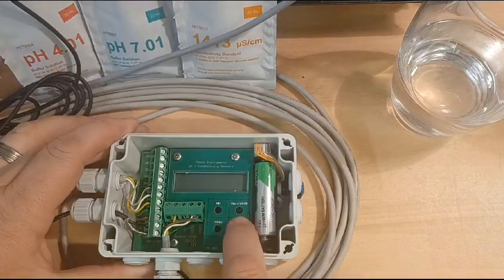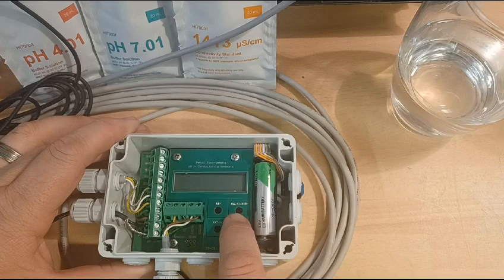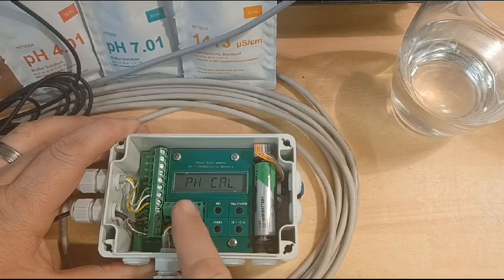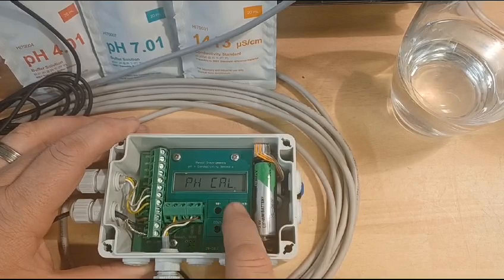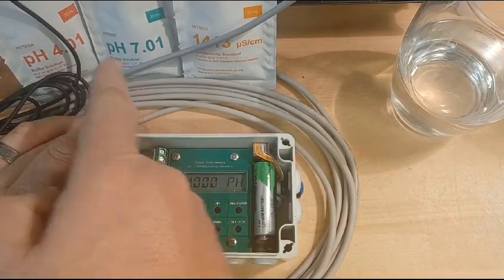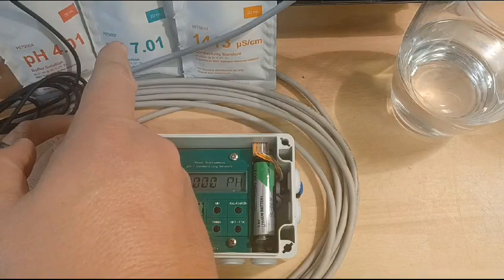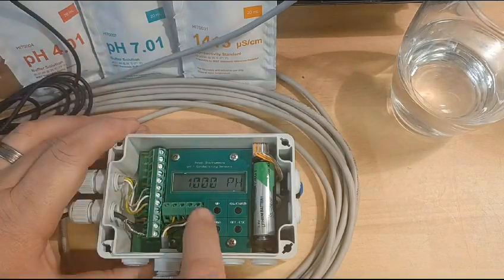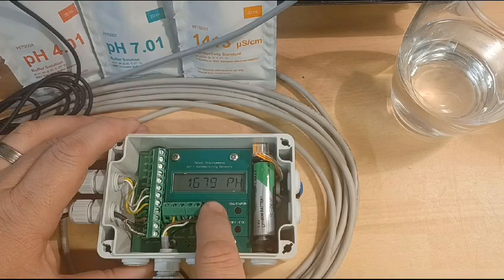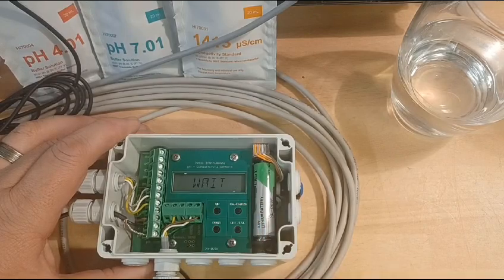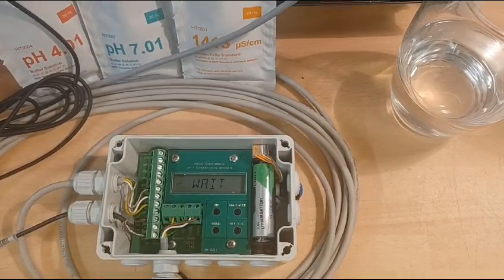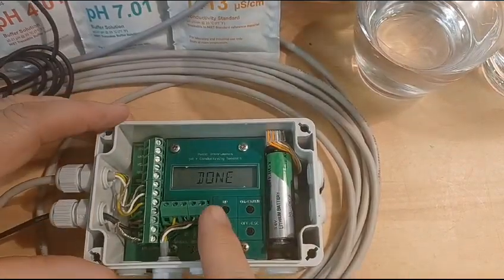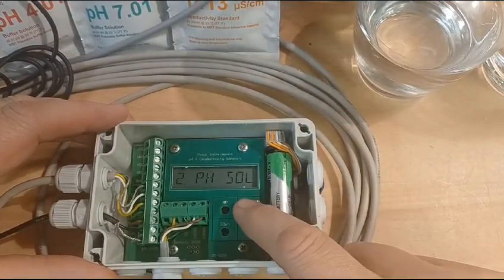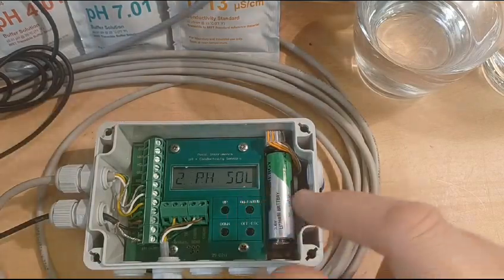And then you select on the enter button, top right, calibration menu. It goes straight to pH calibration. So we want that one, and it's wanting to do the first, because you need to do the two. You always do the higher one first. So you select pH 7. Just scroll up until you get to 7 and then enter, and then it will say wait. After a certain amount of time, you'll then get this message done. You click OK, and now it's asking you for the second pH, which is 4.